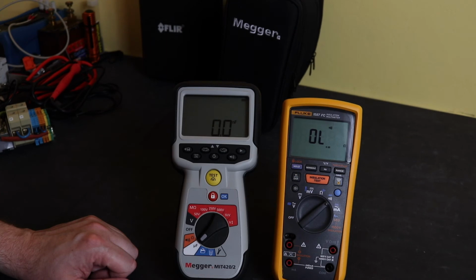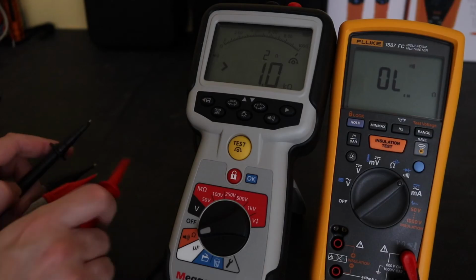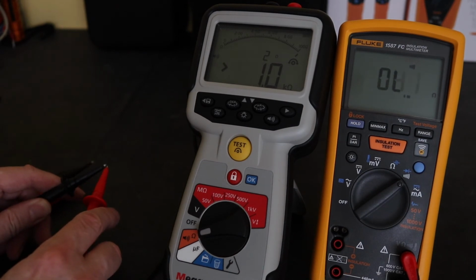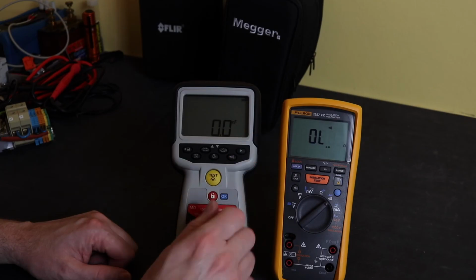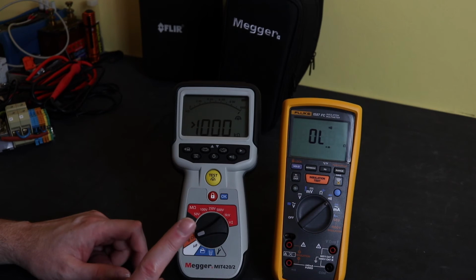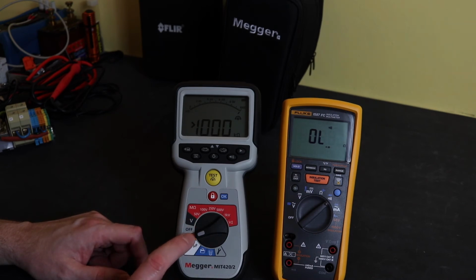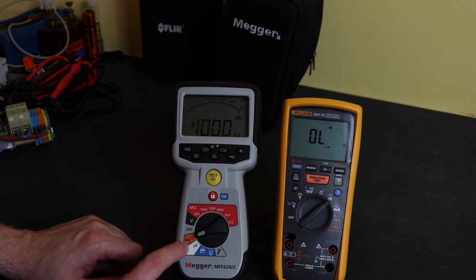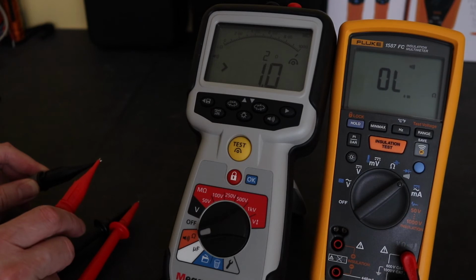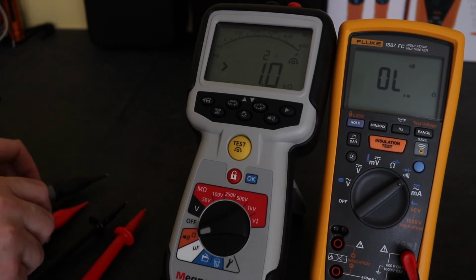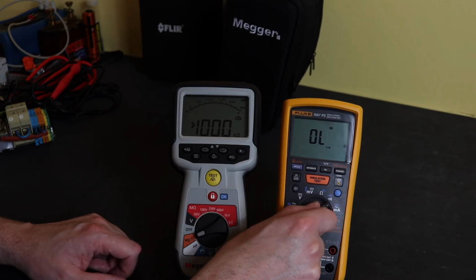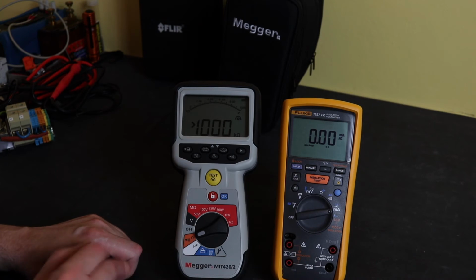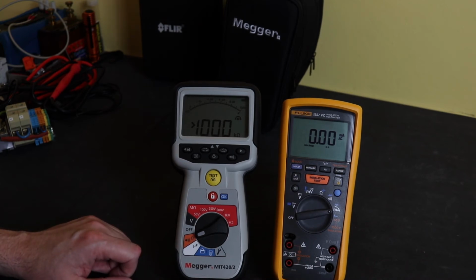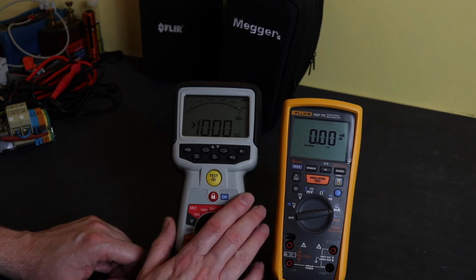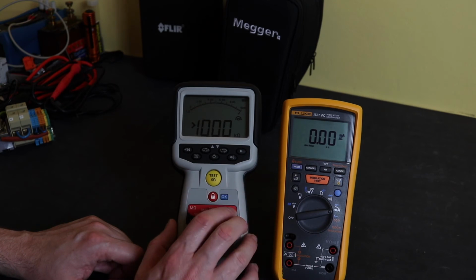If we flip him round, we've got diode and continuity test function on the instrument. You don't have diode test capability on the Megger, but you do have a continuity function built into the automatic resistance function here. And the next one round on the Fluke is milliamps, AC DC milliamps up to 400 milliamps. In actual fact it is 0.01 milliamp up to 400 milliamps. However, the Megger doesn't have any current reading capability whatsoever.